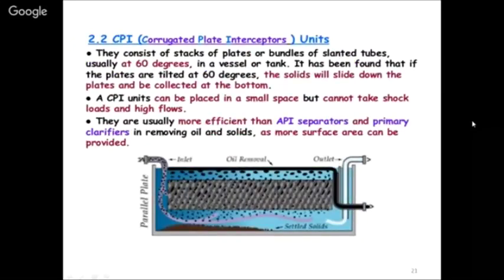The second method for oil separation is corrugated plate interceptors. These consist of stacks of plates and bundles of slanted tubes at a normal angle of 60 degrees in a vessel. By slanting the plates, more surface area is available, improving separation. Solids slide down and are collected at the bottom, while oil rises to the top. This is an improvement over the simple API separator for finer separation.